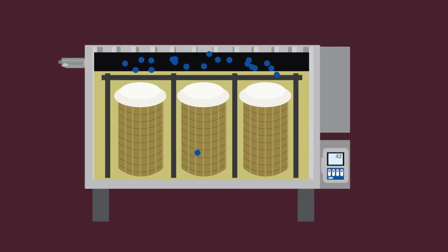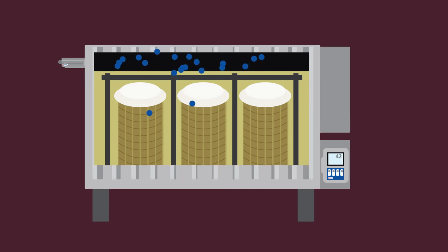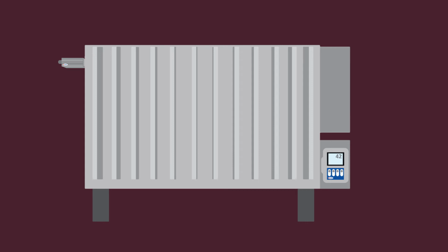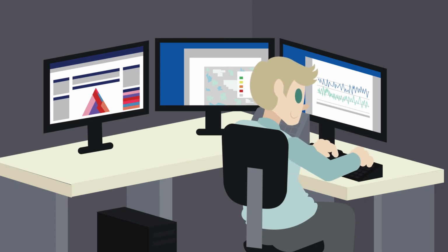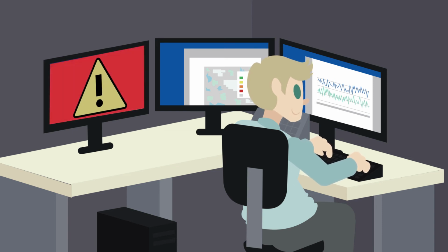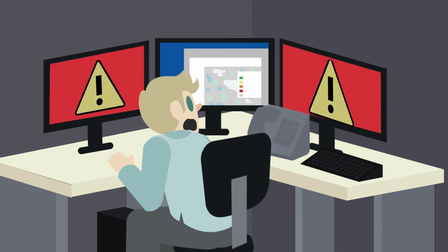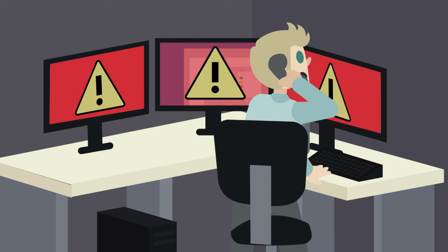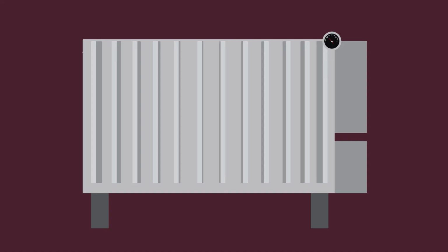Monitoring the headspace can provide a faster detection of problems, and once equilibrium is established, there is a much higher concentration of hydrogen in the headspace compared to the amount saturated in oil. This is usually about 20 parts in gas to every 1 part saturated in oil. Therefore, key gas monitors work very well when installed above the oil level. Key gas hydrogen sensors can be used with a transformer monitor to provide early alarm indication and allow transformers to issue an alert indicating if additional attention is needed.